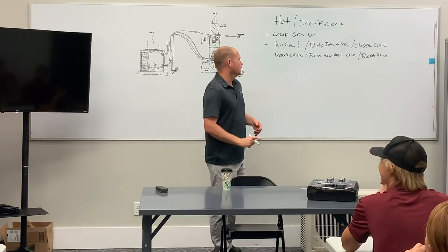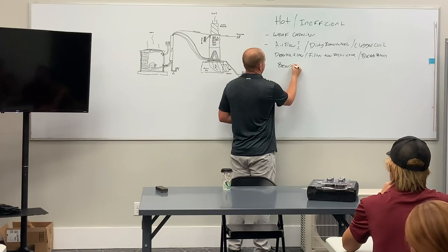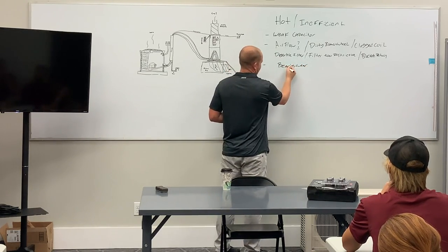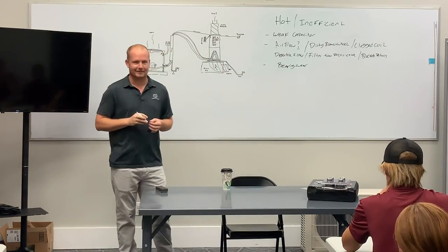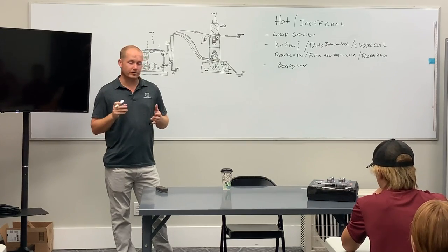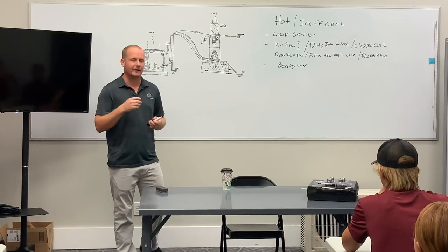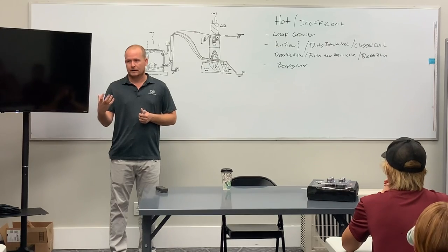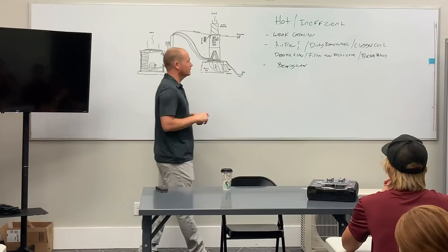That'll do it. Another thing would be bearing wear, right? Bearing. No, this is an A. Like a bear, rawr. Ing. Wear. That'll cause it. And so checking for play in bearings, listening for noises, looking for signs of oil leaking out of the bearings. Those are all things to watch for that can signify bearing wear.